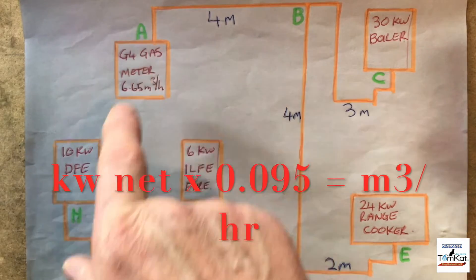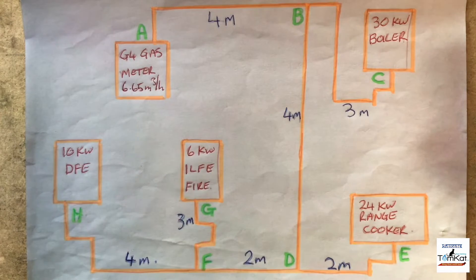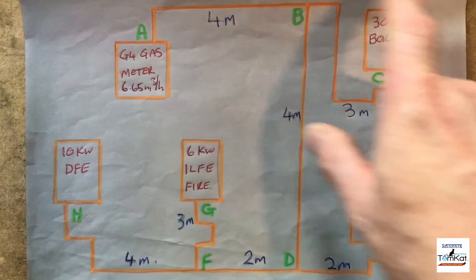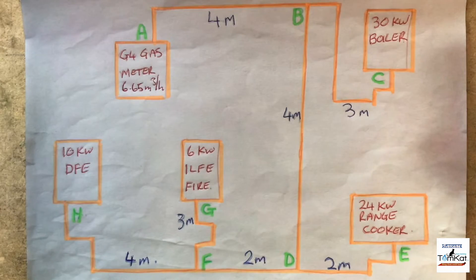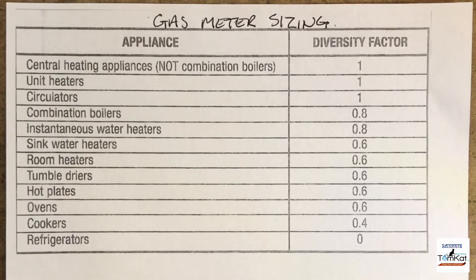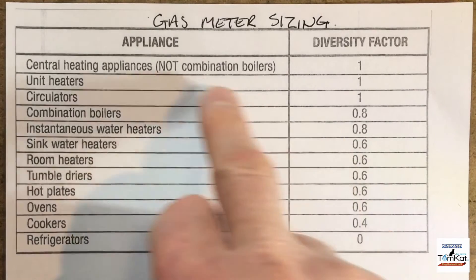This gas meter can only give us six meters cubed per hour, so we need to work out whether this meter is allowed on this installation or not. Sizing a gas meter is pretty straightforward — there are only three steps. Step one: determine the heat input rating of each individual appliance in kilowatts and apply the relevant diversity factor.